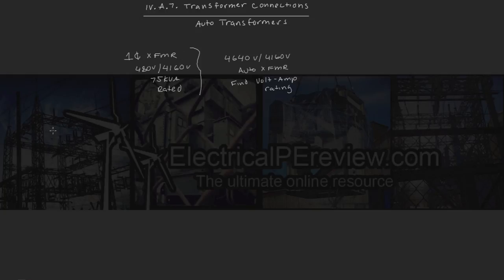First thing we do is we draw our single-phase transformer. Here's our primary winding. Here's our secondary winding. So this could be either a step-up or step-down, depending on which way you look at it, but we're going to draw it in the way it's given to us as a step-up. So 480 volt input, 4160 volt output, and our N1 to N2. If we divide 4160 by 480, that gives us an equivalent 1 to 8.67.